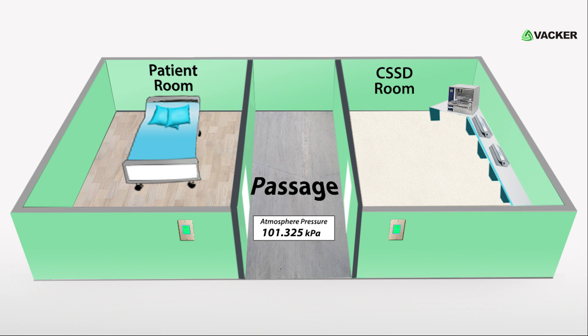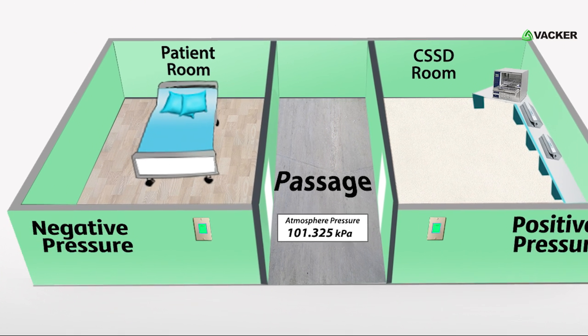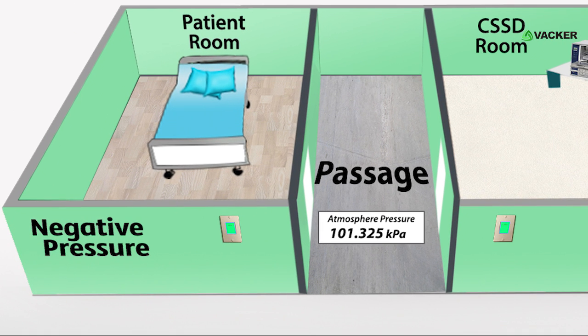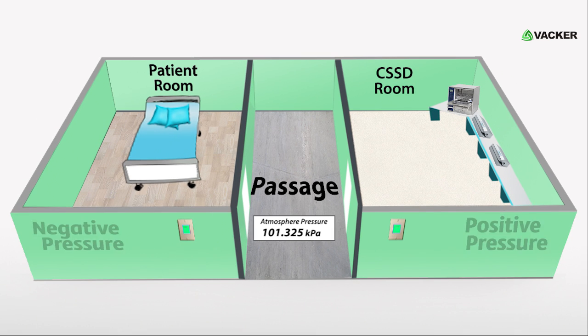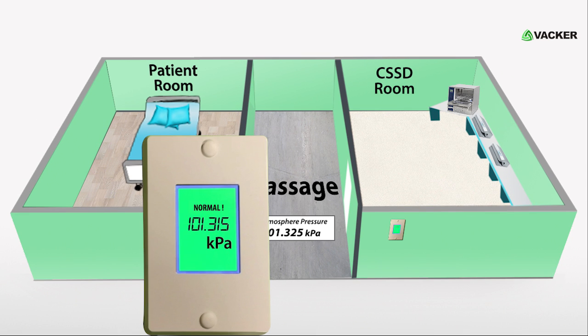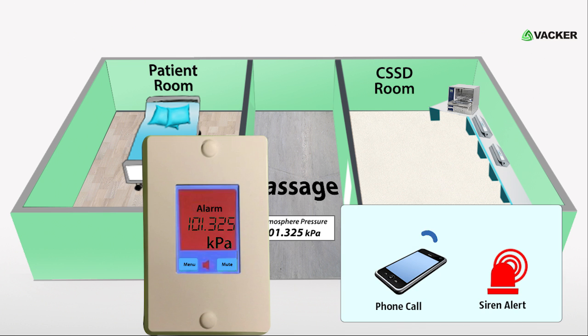In this example, the patient room is at negative pressure and the CSSD room is at positive pressure. When the pressure difference is maintained, the monitoring system will show a green indication. If the pressure difference exceeds the programmed values, the red indication will be activated. It can also generate a phone call alert and a local siren.